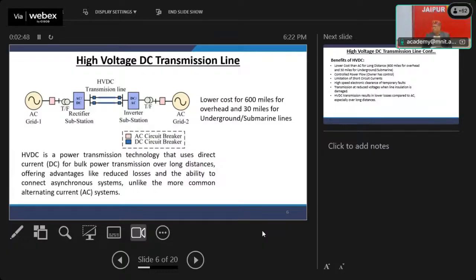So I think what has been proven as of now is, if you go for a very, very long transmission, HVDC is beneficial. For short transmission, HVDC will experience more loss. The transmission loss will be reduced, but the switching losses will be very significant. But if you go beyond 600 miles, or underground up to 30 miles, then probably people say HVDC is much more meaningful than your HVAC. Next, please.